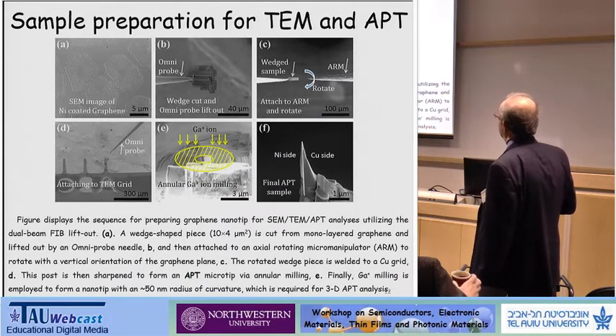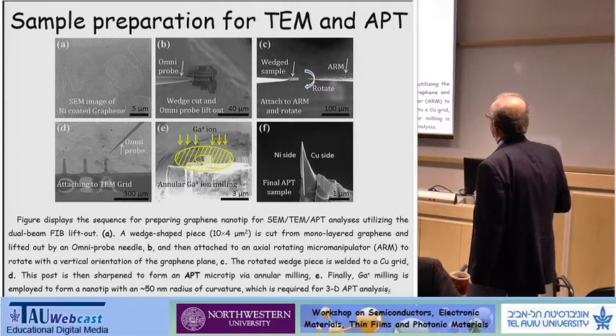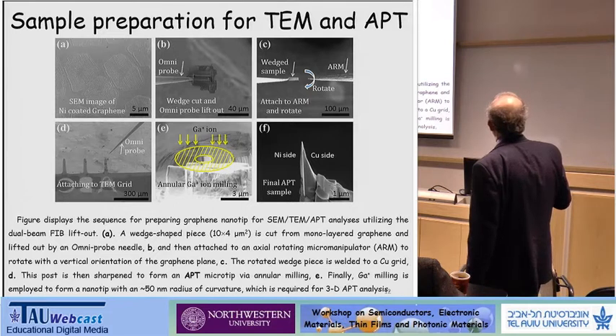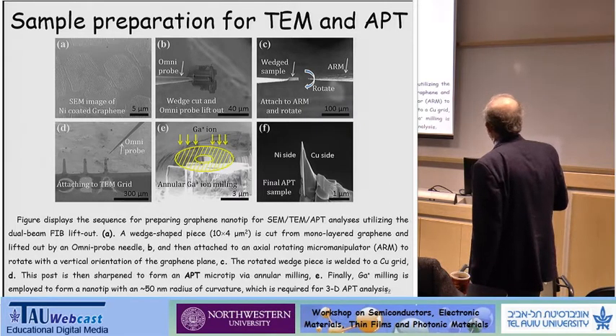So here's how you make the specimens. This is the SEM micrograph I showed you already. Then on top of the specimen, nickel is deposited. With the dual beam FIB microscope, we mill out a specimen that has a triangular cross-section. So it's a wedge-shaped specimen, and you pick it up with an Omniprobe, and then here is that same piece. Then we use what's called an ARM, and that allows us to rotate the specimen and align the interface such that it's along the long axis of this nanotip. We can also put the specimen first on a TEM grid to analyze it using transmission electron microscopy, and then ion mill it into the shape of a nanotip, and this is your specimen.